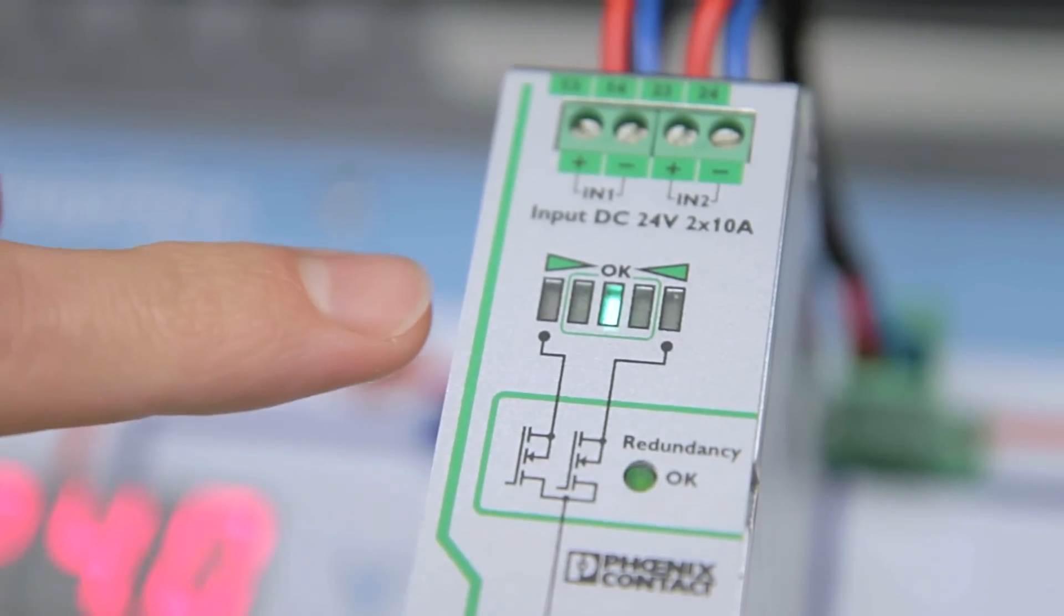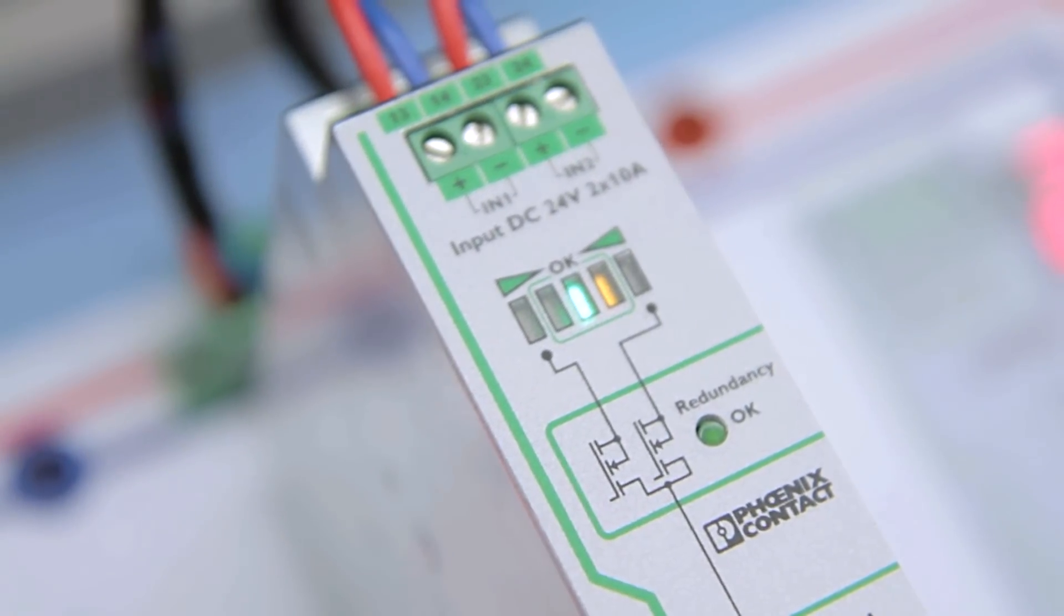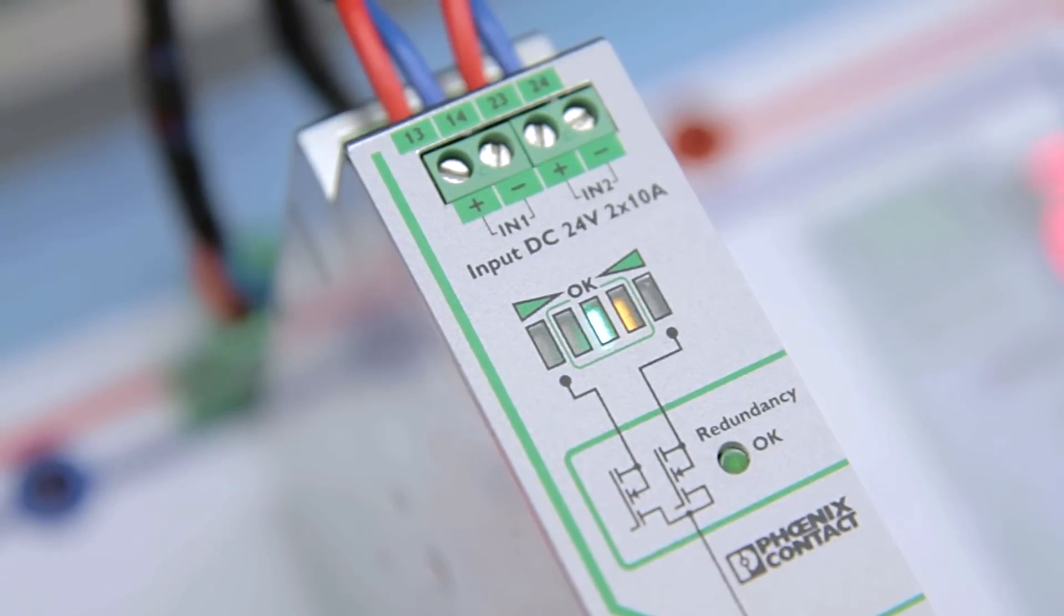Even load sharing is indicated on the display by a green light. When the voltage of the power supplies start to drift, the O-Ring module will keep the current balanced. However, a yellow indicator will show that the redundant power supplies are no longer adjusted properly.